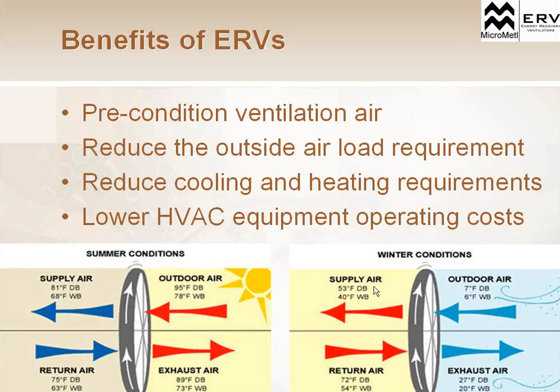Now, the latent energy works backwards in winter, where we actually want to maintain humidity in our space. We go from a 6-degree wet bulb up to a 40-degree wet bulb. So we keep the humidity inside the space during the winter, and during the summer we keep the humidity outside of the space. That's why we call it an energy recovery ventilator. We're getting both that sensible and latent energy transfer. So we're getting the temperature change, and we're getting the moisture in or out of the building depending on the season.